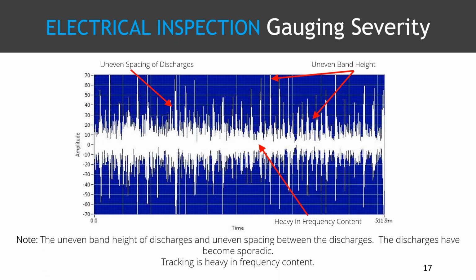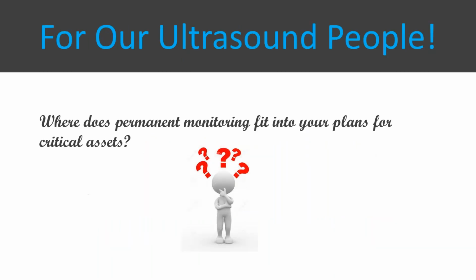You can see a good example here—this is very severe tracking. Notice the uneven band height, with some discharges very loud and some very soft in amplitude. You can see uneven spacing, with some discharges further apart and some very close together. There's also a high degree of frequency content—some discharges last longer and are fat, others are very narrow or thin. This tells us we have an extremely damaged component, with a lot of tracking bordering on arcing. This is a very severe condition.